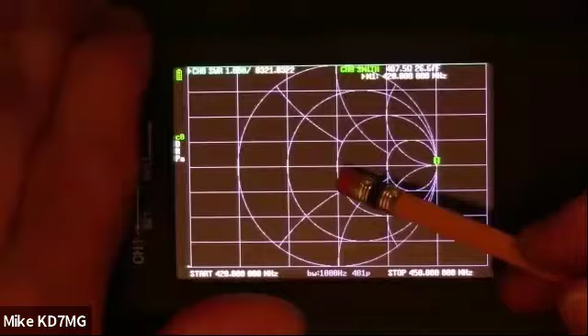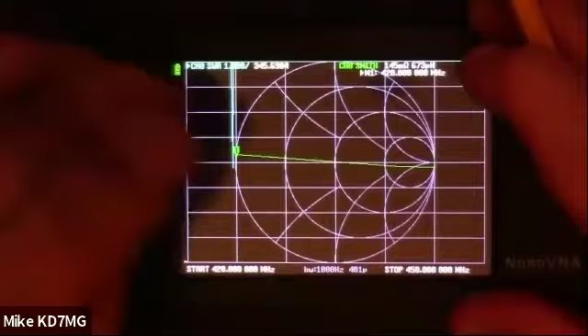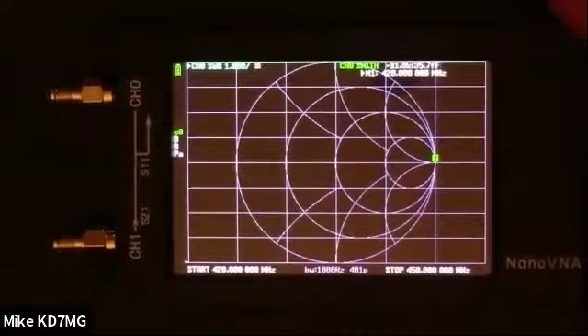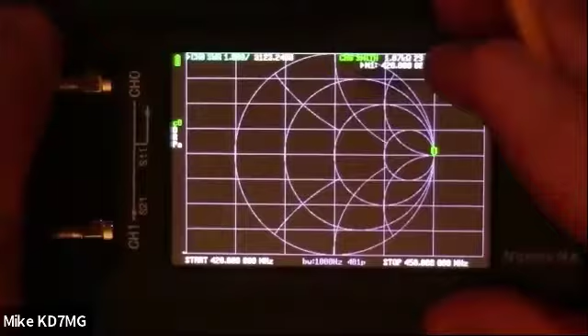So by doing the 3 standard calibration, the open short load, some people call it SOL, we can see right now we did our calibration at the full bandwidth. Now we narrowed it down. Now we have 400 data points from 420 to 450. Okay, that's a whole lot less than 4 megahertz per data point. Let's put on the short. As I screw it on, you can see it draw down right to where it's supposed to be.